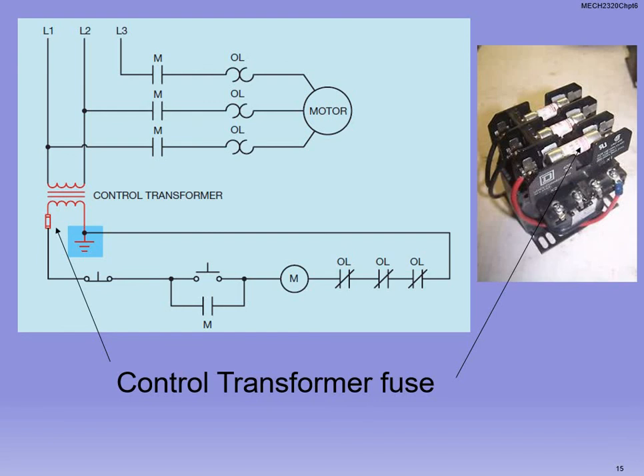Okay, let me break this down to the big picture for you before we wrap things up here. If you look at line 1, line 2, and line 3, that's the main power going to the motor so that the motor runs. Okay? And we've talked about the motor contacts, we've talked about the overload relays, we're taking a look at the schematic. Gradually, you need to understand everything that's on these schematics as we go through them. Notice that the control transformer taps into the main power that also feeds the motor. So that's why I was saying before, it depends on the voltage coming into that control transformer. So we need leg 1 and leg 2. You're not sending 3 legs of power in there. That control transformer steps everything down into our 24 volt potentially, or whatever our control voltage is that we're using there. So we obviously protect it with the fuse.